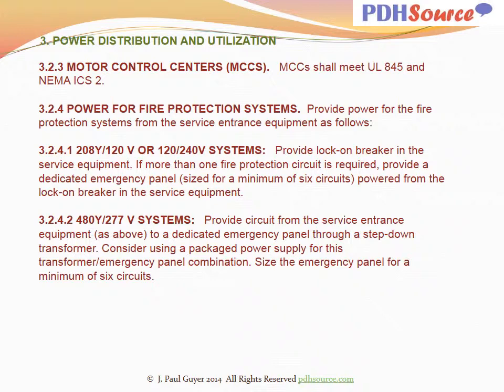If more than one fire protection circuit is required, provide a dedicated emergency panel sized for a minimum of 6 circuits powered from the lock-on breaker in the service equipment. 480Y/277 volt systems: provide a circuit from the service entrance equipment as above to a dedicated emergency panel through a step-down transformer. Consider using a packaged power supply for this transformer and emergency panel combination. Size the emergency panel for a minimum of 6 circuits.